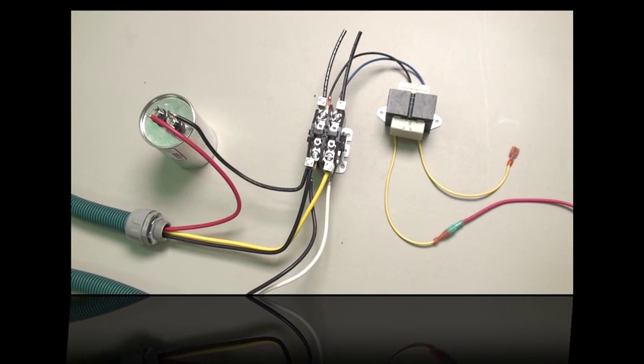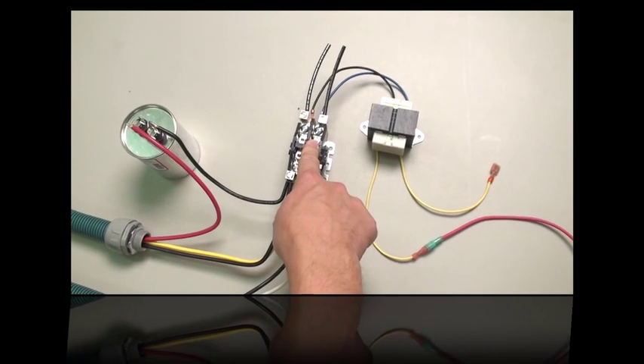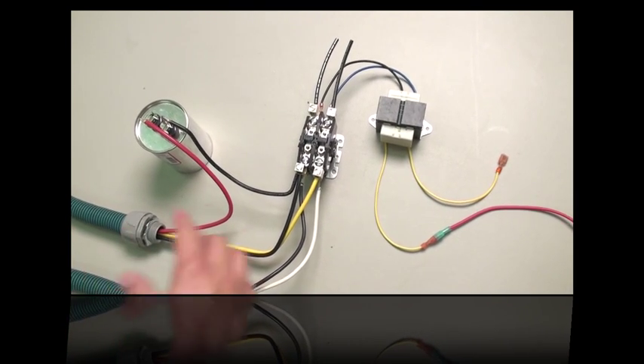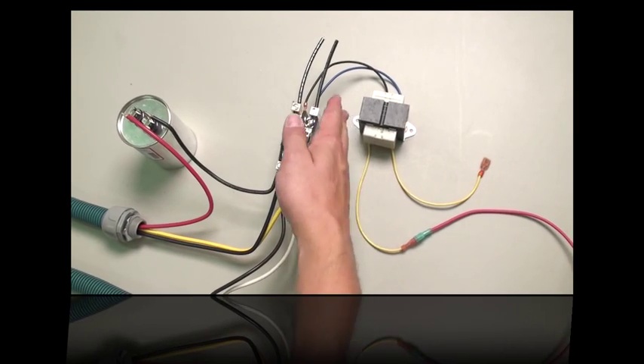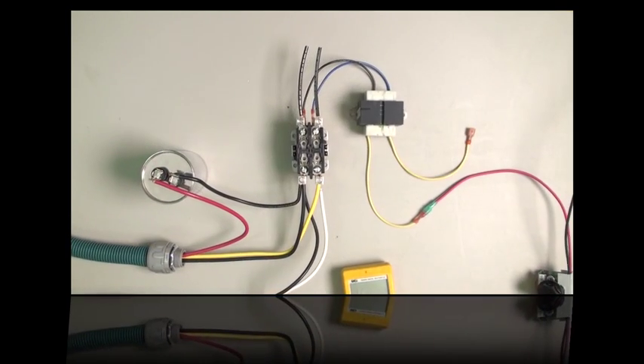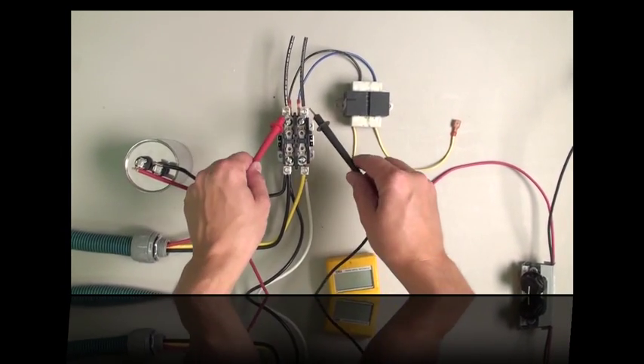If the heat pump won't start, that's an indication that the contactor is not pulling down — otherwise you would have some symptom of running in some shape or form. Not starting typically means it has to do with the 24-volt circuit or the 240 volts coming in. So the first thing to do is check to make sure there's 240 volts at the unit.